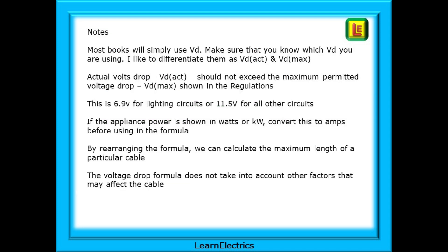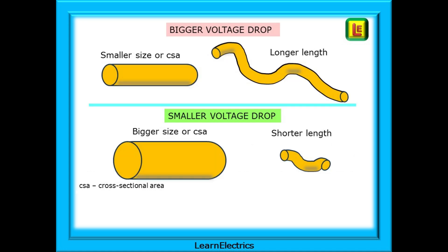A few notes as a recap on what we've talked about. Most books will simply use VD. Make sure that you know which VD you're using. I like to differentiate them as VD(actual) and VD(maximum). Actual volts drop VD(actual) should not exceed the maximum permitted voltage drop VD(max) shown in the regulations. This is 6.9 volts for lighting circuits or 11.5 volts for all other circuits. If the appliance power is shown in watts or kilowatts convert this to amps before using in the formula. By rearranging the formula we can calculate the maximum length of a particular cable. The voltage drop formula does not take into account other factors that may affect the cable.